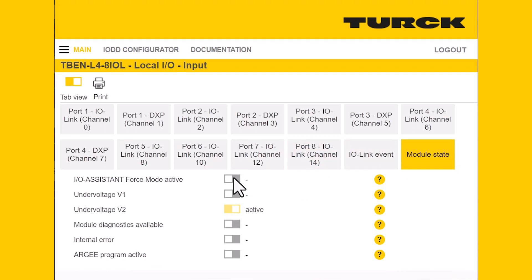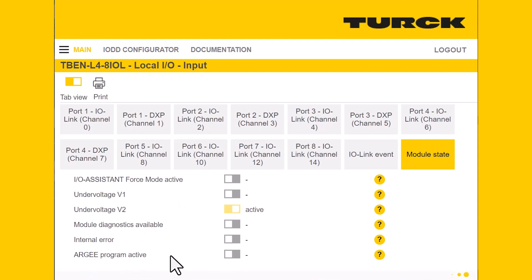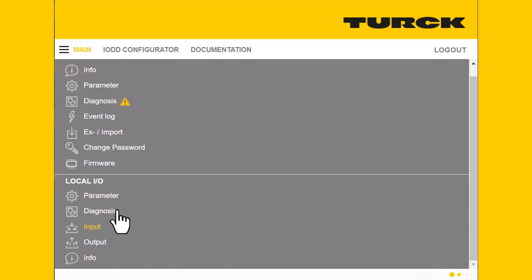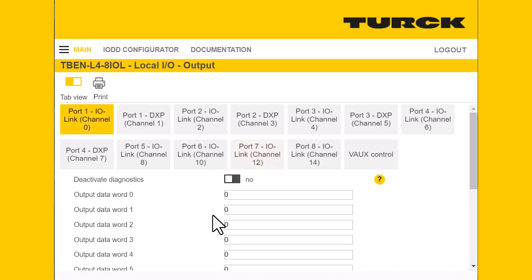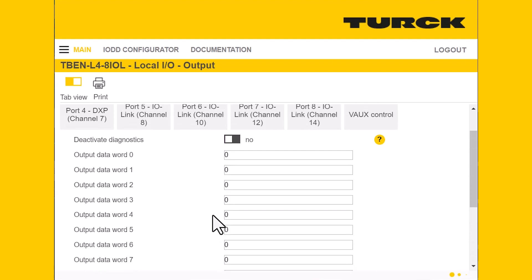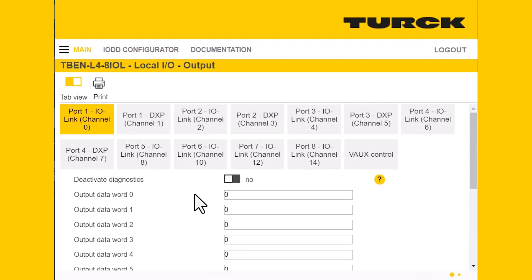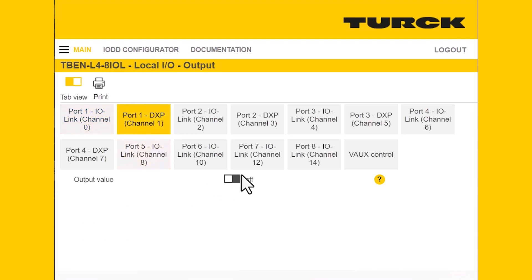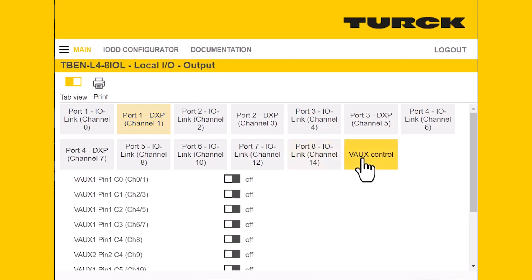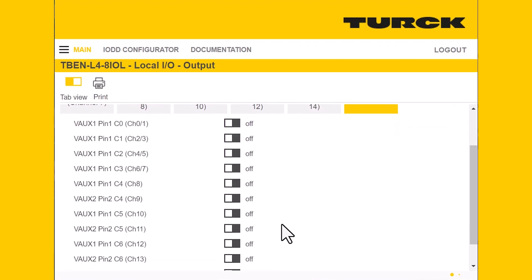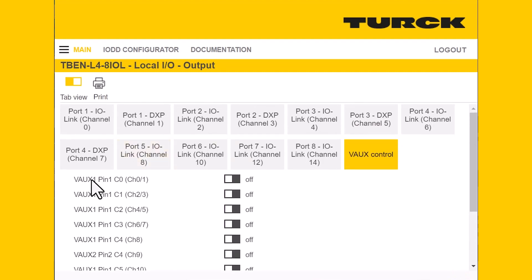Next, we'll do our module state input. You can see that undervoltage at V1 is turned off, while undervoltage at V2 is currently active. It will also let us know if there's an ARGEE program running on the device. Moving to the output tab — we don't have any outputs turned on right now, but similar to the input tab it's broken up by word and will show you any values. For your DXP pin, it tells you whether your output is on or not, and for your auxiliary power control, you can manually turn those on here as well.